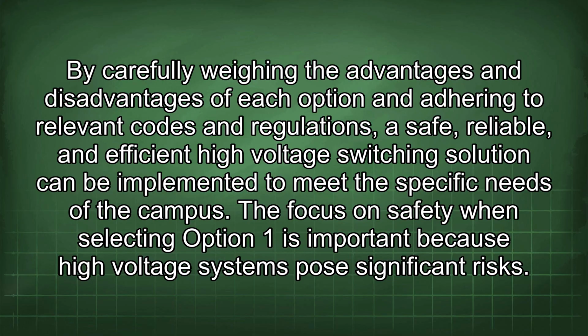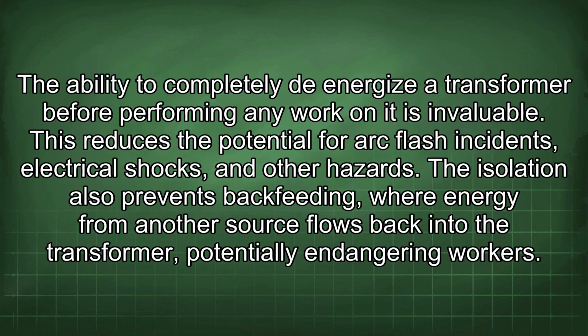The focus on safety when selecting option 1 is important because high-voltage systems pose significant risks. The ability to completely de-energize a transformer before performing any work on it is invaluable. This reduces the potential for arc flash incidents, electrical shocks, and other hazards. The isolation also prevents backfeeding, where energy from another source flows back into the transformer, potentially endangering workers.